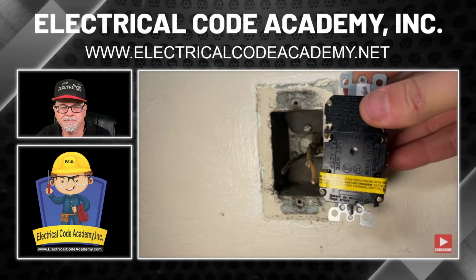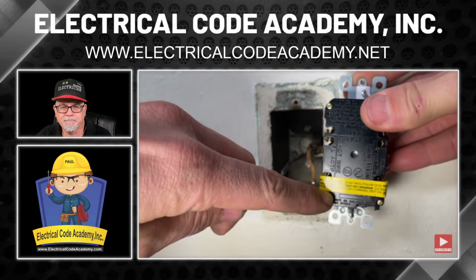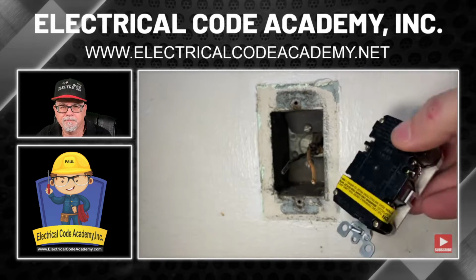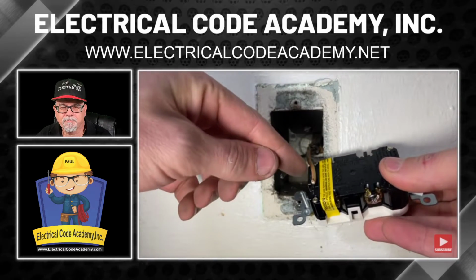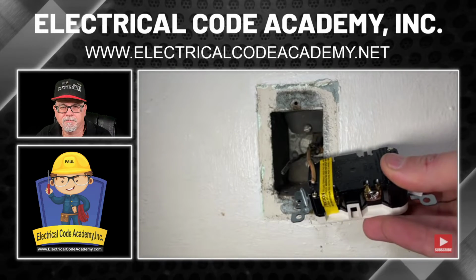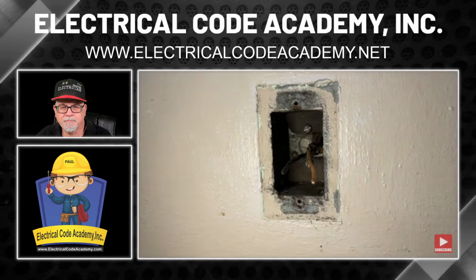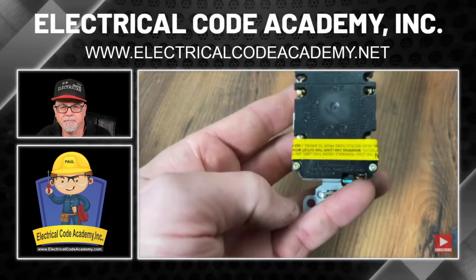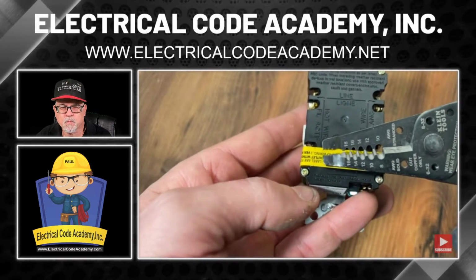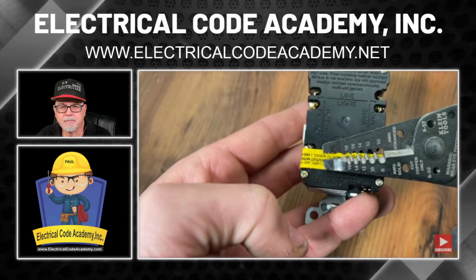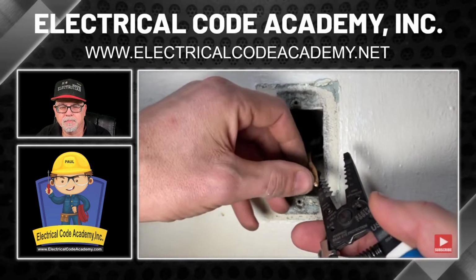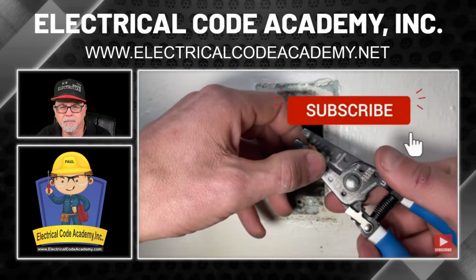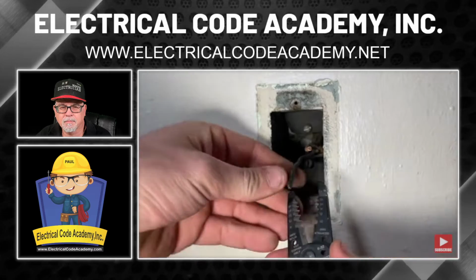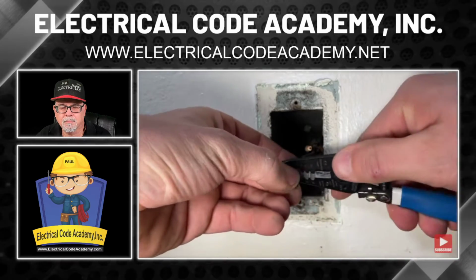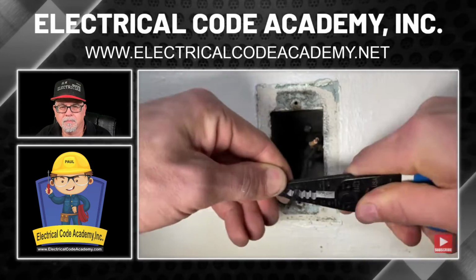GFCI and all receptacles really have a strip gauge that will show you how much copper you need to strip to properly install. You can use the strip gauge like this to reference your line, or what I do is I actually take my strippers and just get a reference on the strippers. So I know I need to strip to the 14 gauge mark on my strippers, take that mark, pivot strippers, and then strip that amount of insulation off. So I'll do that on the neutral and on the hot side. So we're ready to start wiring.